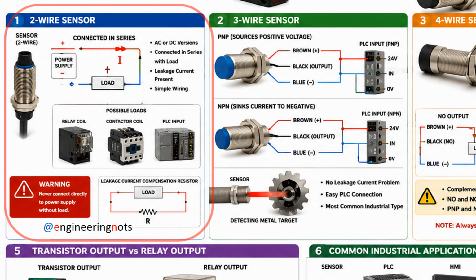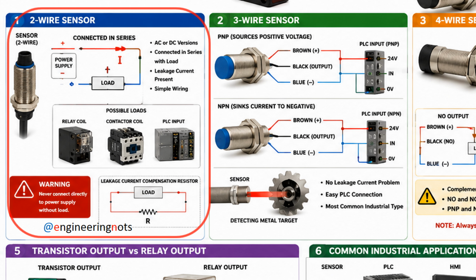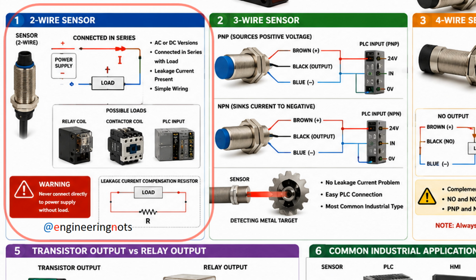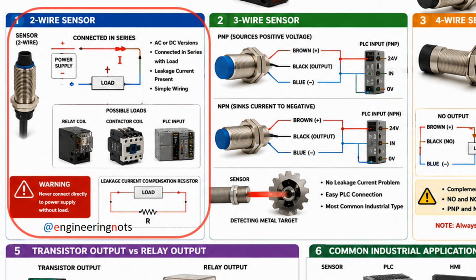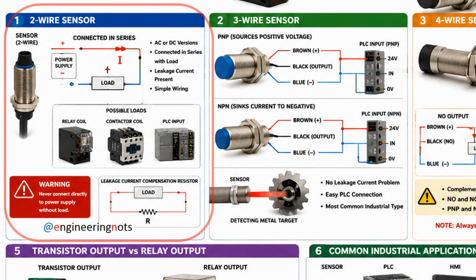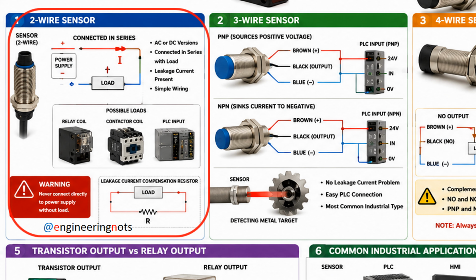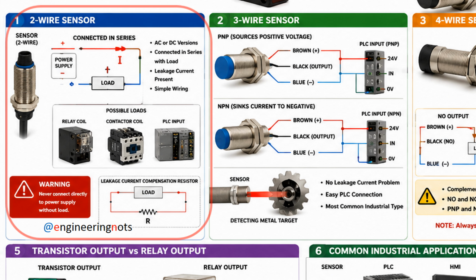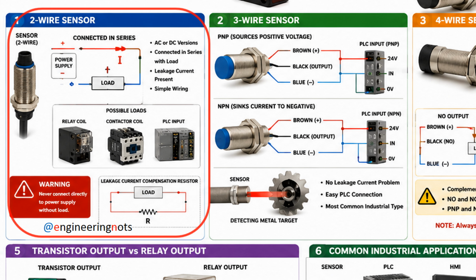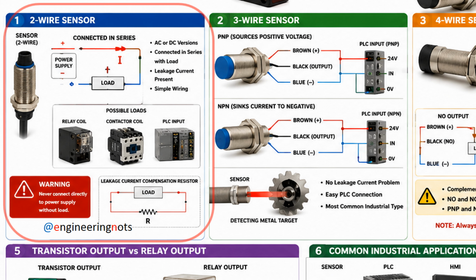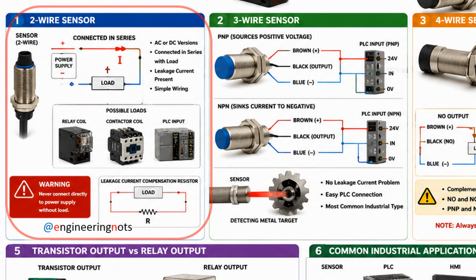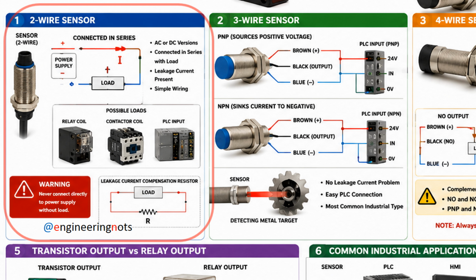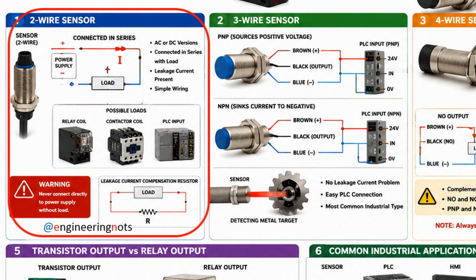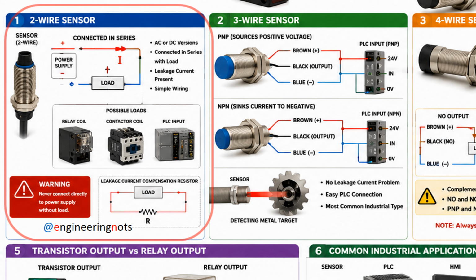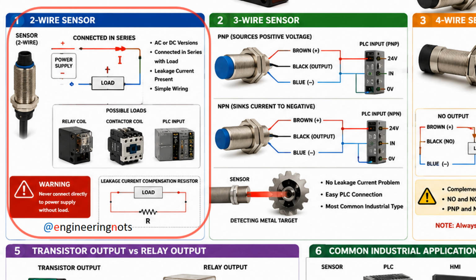Solution. To solve this problem, a resistor is connected in parallel with the load. This resistor carries the leakage current. As a result, the load is no longer affected by the leakage current. Advantages of two-wire sensors. Simple wiring. Fast installation. Suitable for replacing switches. Disadvantages of two-wire sensors. Presence of leakage current. Limitations when connected to some electronic inputs. Less flexibility compared to newer sensor models.